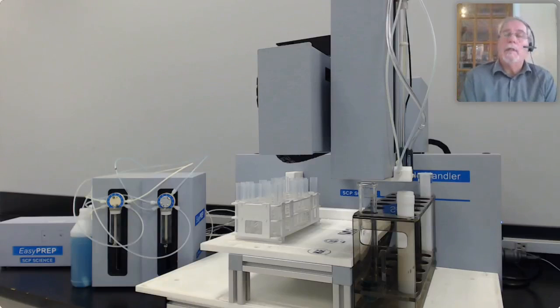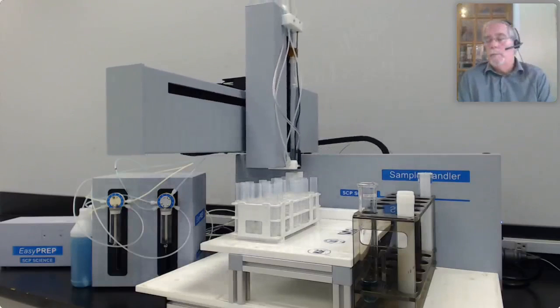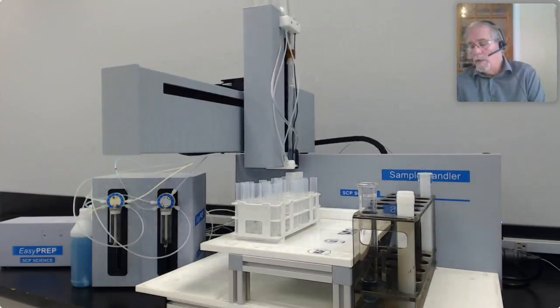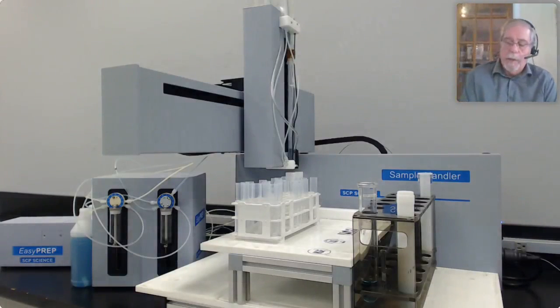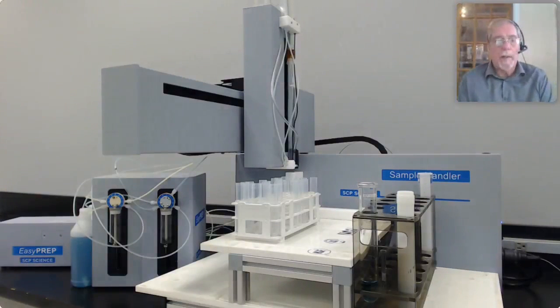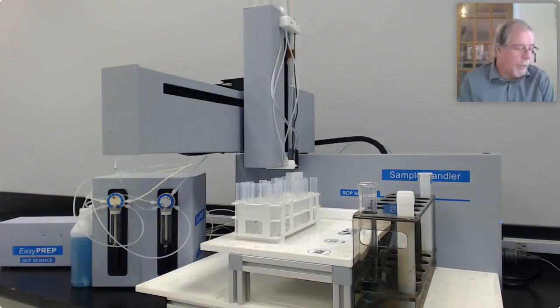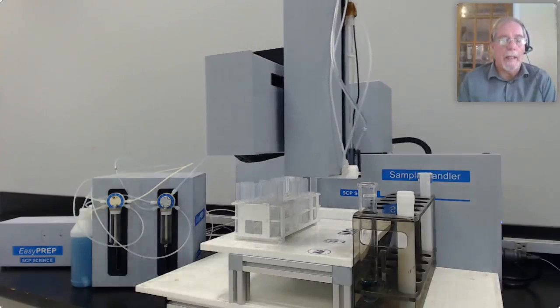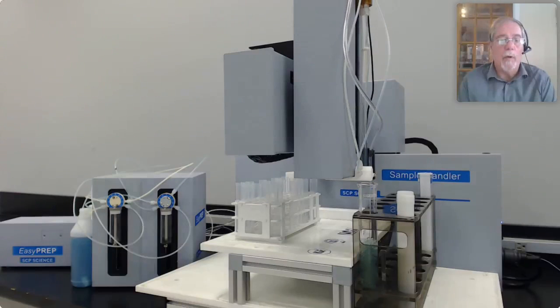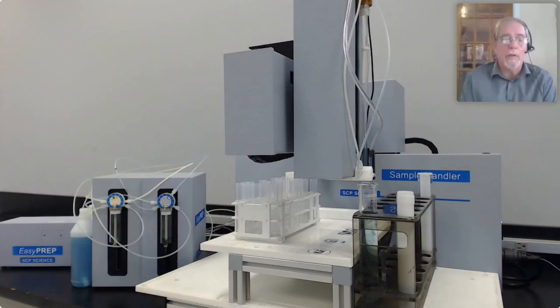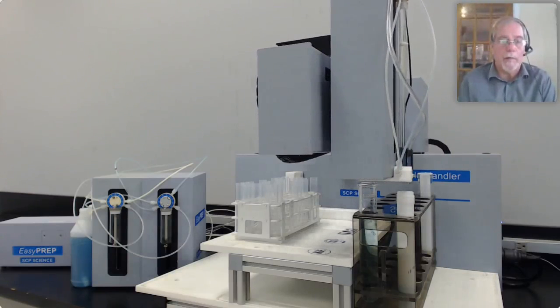We would then take the tubes, cap them, put them in the microwave, run the digestion sequence, cool the samples, uncap them, put them back on the sample handler, and now we will run the normalization. We're going to use the bulking pump to normalize here. So we're going to just add an aliquot of 40 mils to each tube so that you can add a volume. This is to show you the speed and the mixing capabilities of just dispensing the diluent through the bulking pump.